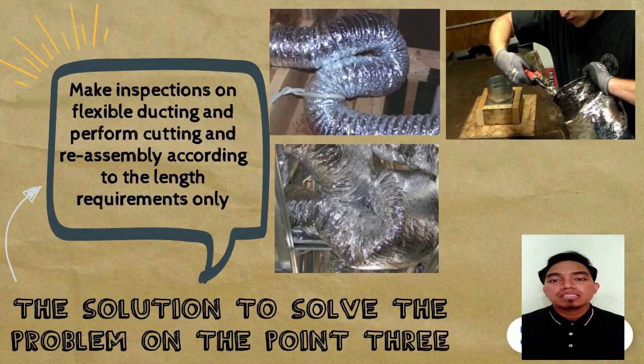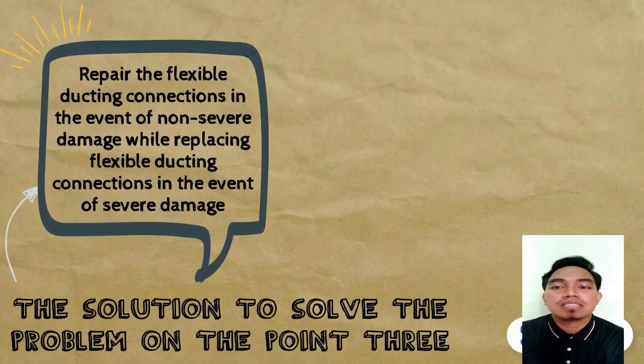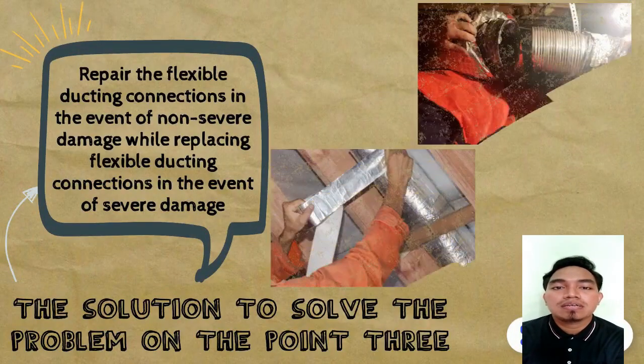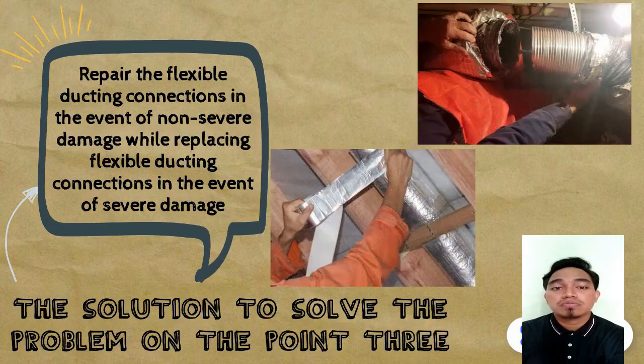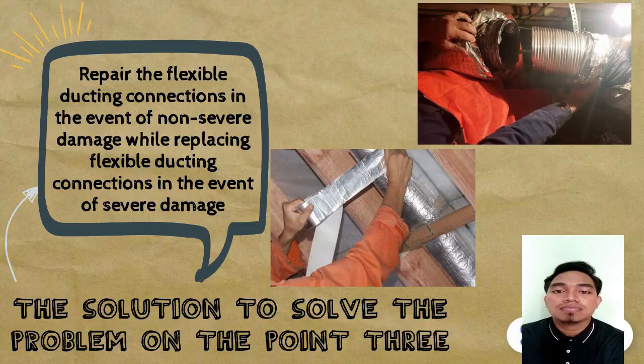This is because if there is a fault in the flexible ducting, it will cause the air to pass through a long distance and hit many surfaces, therefore high pressure loss will occur. The last one is to repair the flexible ducting connection in the event of non-severe damage, while replacing the flexible ducting connection in the event of severe damage.